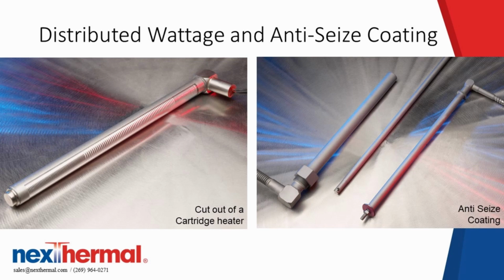And here's a cutout of a cartridge heater where you have more windings at the cap end and at the lead in, or in this case, the right angle. That's how we distribute the wattage. It's a CNC control method. And then on the right is our anti-seize coating. How we do that is we centerless grind the cartridge heater a little bit undersized in the diameter, and then when we apply the coating, we bring it back up to tolerance.